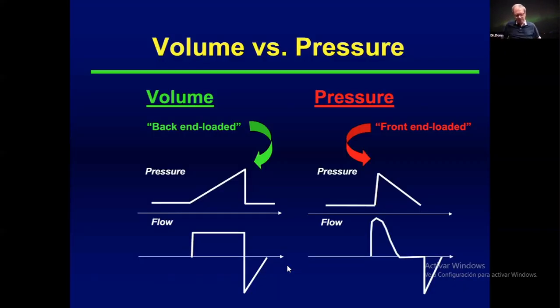Now, this is probably the most important slide that I've included in the lecture because it shows you the differences between volume targeted and pressure targeted breaths. And let's start on the right side of the slide in red, the typical pressure limited or pressure controlled breath. What happens when the breath begins is that there is a rapid acceleration of inspiratory flow, which peaks very early in inspiration, then rapidly decelerates back to the baseline. And what this does is it creates the so-called shark fin pressure waveform. And you'll note that peak pressure and peak volume delivery occur very early in inspiration. So I like to refer to this as a front-end loaded breath, meaning that you get most of the pressure and volume delivery occurring early in inspiration.